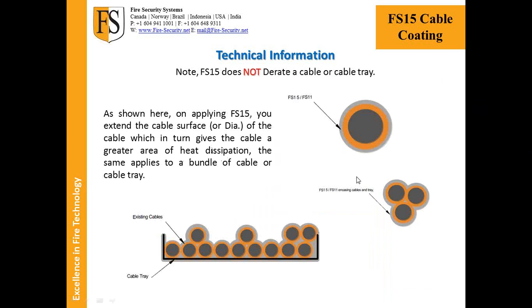So here we talk about FS15 not derating a cable or a cable tray. As shown, whether in this group, in this bundle, or this cable tray, when you are applying FS15 to its 1mm DFT, even to its 1.6mm FM dry film thickness, you're extending the cable surface. You're extending the diameter of the cable, creating a greater surface area on the outside diameter for the heat to dissipate out and keep that cable cool. Is this also valid for intumescents for inside applications? Yes, it is.